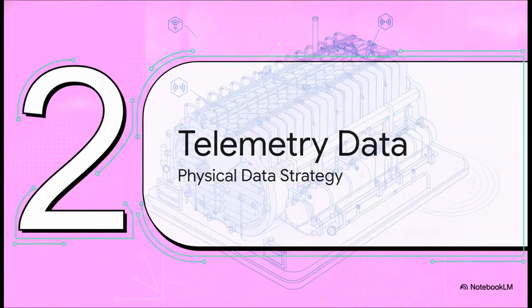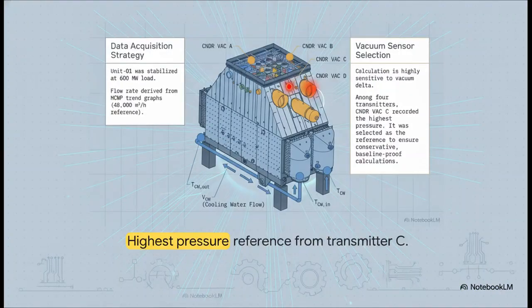Section 2, telemetry data. So where are we actually getting our numbers? Look up at the top of the condenser schematic here. Notice we have 4 vacuum transmitters, A, B, C, and D. Now, our math is incredibly sensitive to the vacuum delta. So among these 4, transmitter C, or VAC C, actually recorded the highest pressure, and we deliberately selected it as our reference point. You might be wondering, why pick the worst case scenario? Well, to make sure our calculations are conservative and totally defensible. By taking that worst-case, highest pressure reading, our final cleanliness assessment becomes practically baseline proof. We're not artificially inflating our success here, for sure.